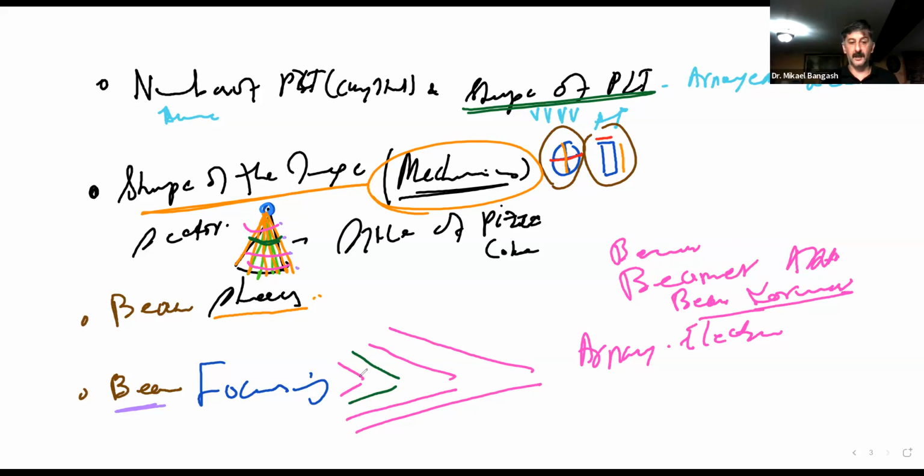And when you form the beam, you say, well, focus at this point here. Focus at this depth here, focus at this depth here, focus at this depth here. Because I want you to produce a beam that gets to its narrowest point at this depth, or this depth, or this depth. Technically, what we do is choose the number of focal points and place those focal points as we want to. The rest is going to be up to this beam former to produce the beams that will be focusing at the focal points that we have chosen, and that number.